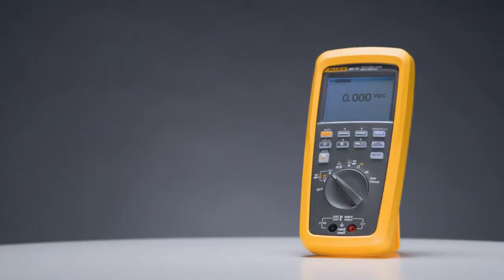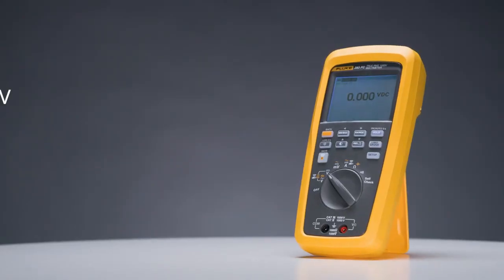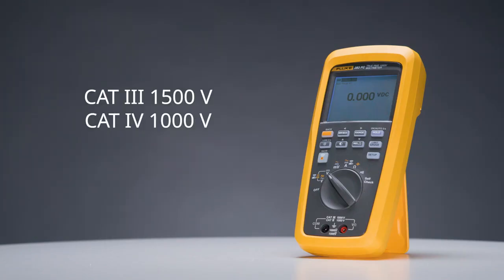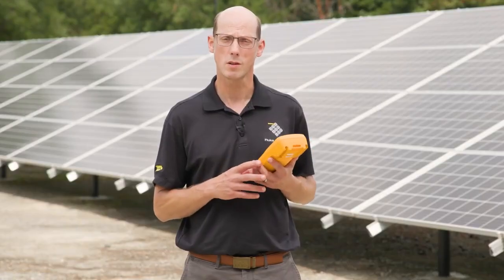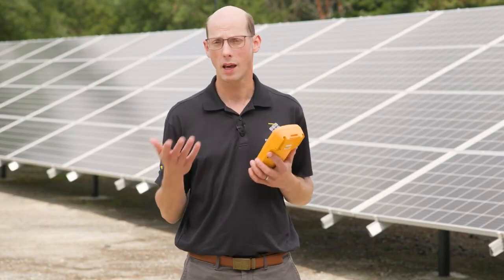The 283 FC multimeter is our category 3 1,500 volt, category 4 1,000 volt digital multimeter, which is an excellent choice for testing those high voltage utility scale systems, both on the DC side and the AC side, where our outputs may be up to 800 volts or even higher.